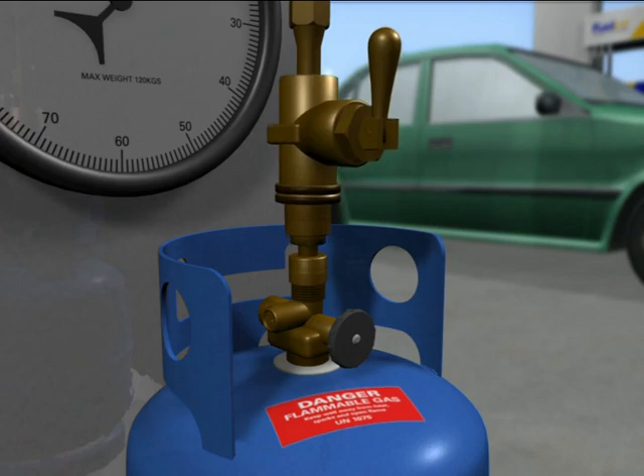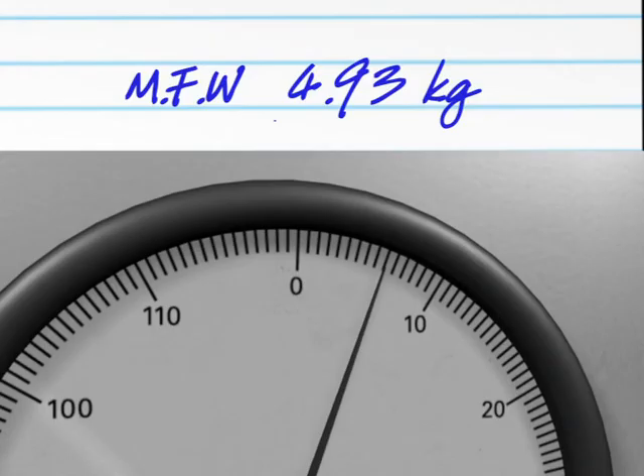Disconnect the hose assembly. Check the weight reading on the scales. If it's more than 100 grams above the maximum full weight, treat it as being overfilled.